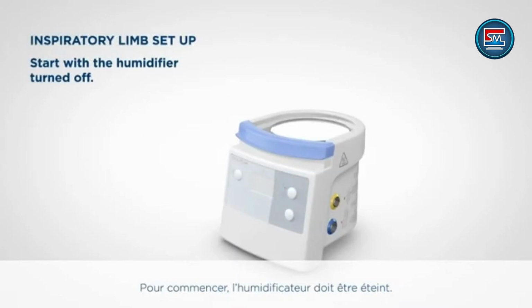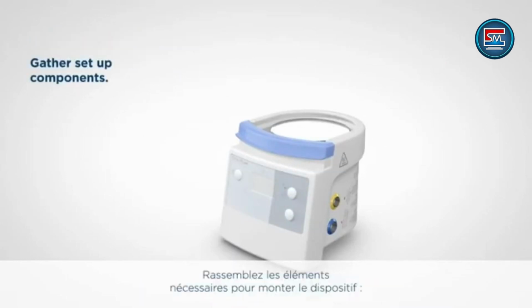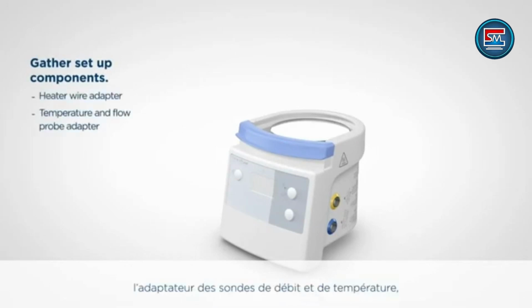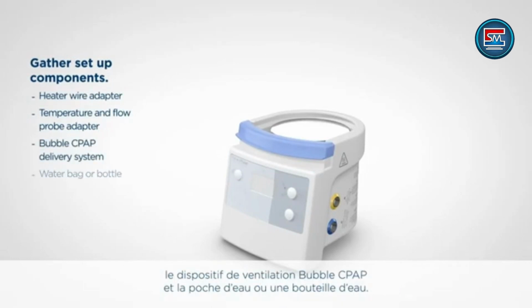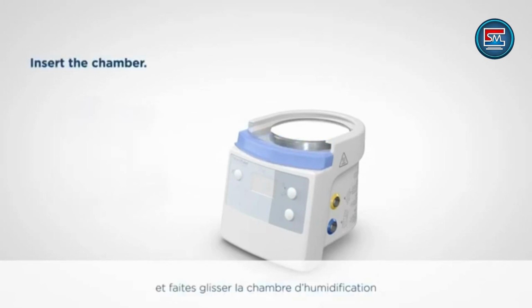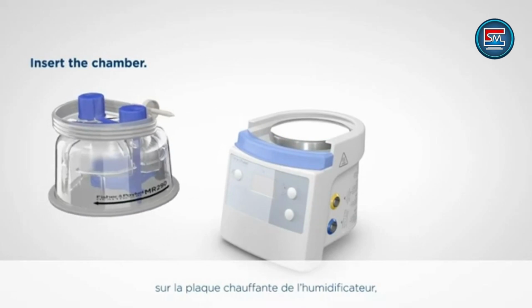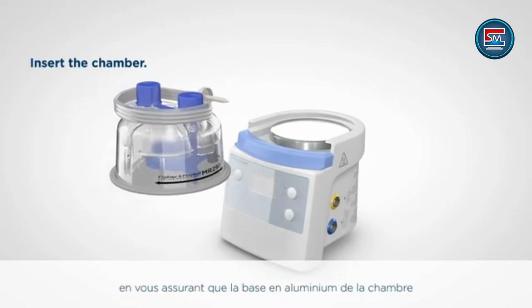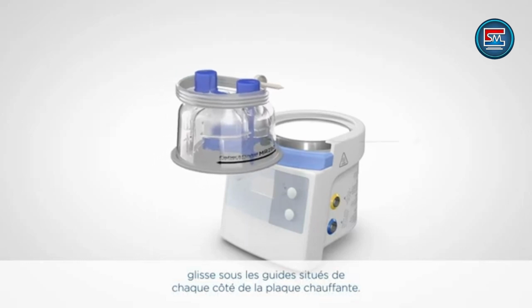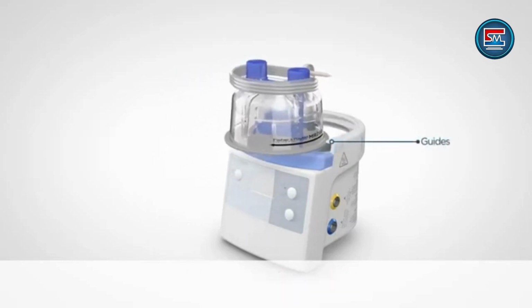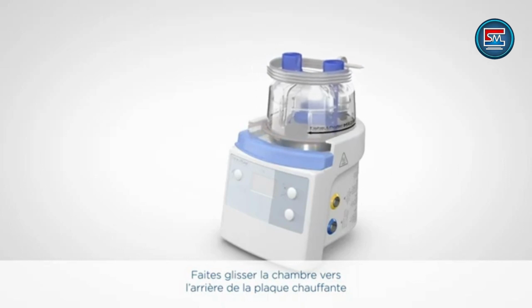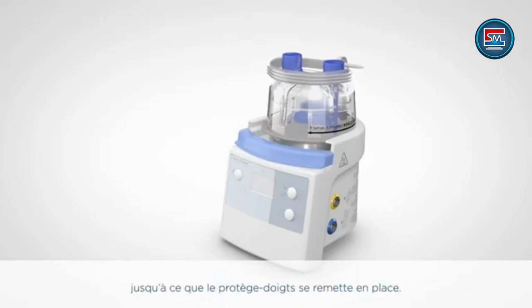Start with the humidifier turned off. Gather the components required for setup, including the heater wire adapter, temperature and flow probe adapter, Bubble CPAP delivery system, and water bag or bottle. Open the Bubble CPAP delivery system bag and take out the humidification chamber. Push down the finger guard and slide the humidification chamber onto the humidifier heater plate, making sure the aluminium base of the chamber slides under the guides on either side of the heater plate. The chamber should slide to the back of the heater plate until the finger guard springs back to place.